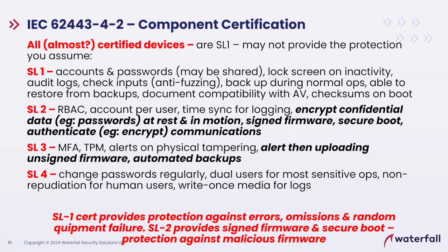If you're logged into the device, it gives you a lock screen if you go inactive and you have to give the password again. It gives you some security logs, like someone just logged in, someone just logged out. It does some input checking. The features are not very secure. They're basically a little bit of protection against errors and omissions.